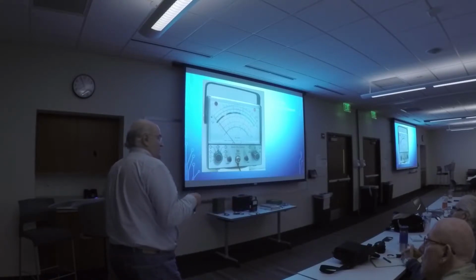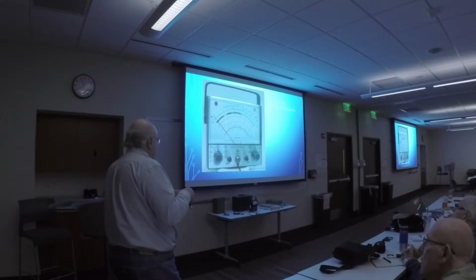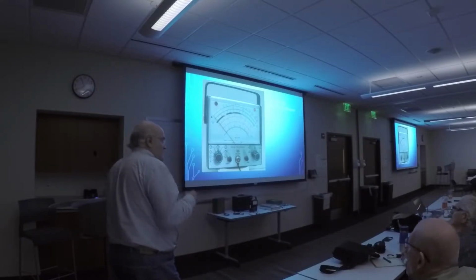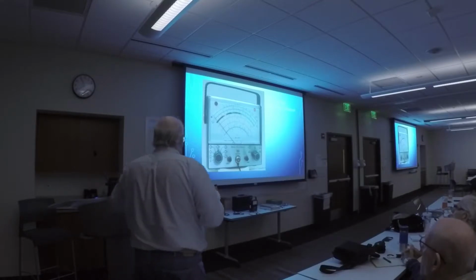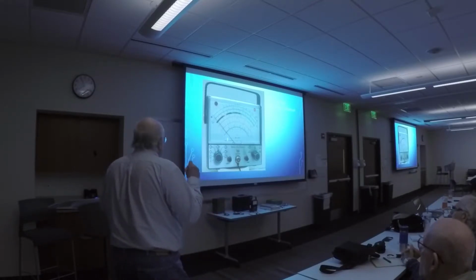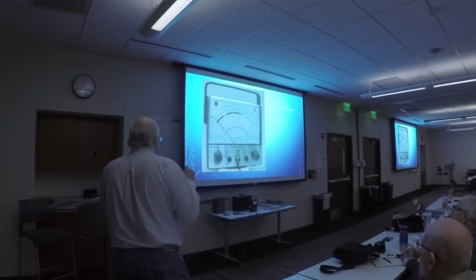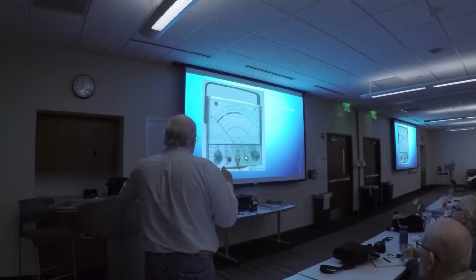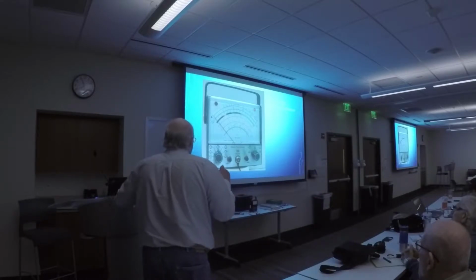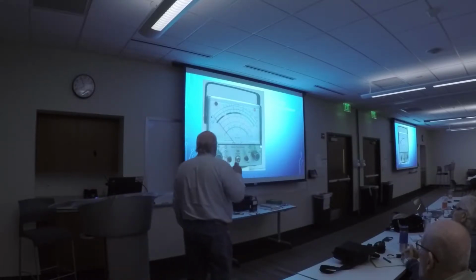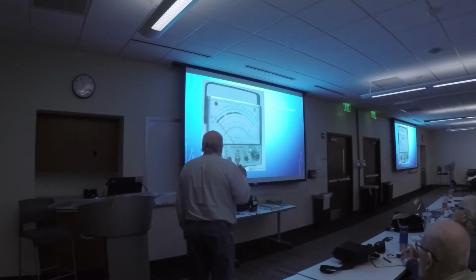You take the isolation lead and hook that to the minus, the negative, the ground, and then you adjust your 0. Because like I said, it's very, very sensitive. It will pick up stuff out of the ether, because it's so very sensitive. Now this center thing here, I'll come back to that in a second. That's an interesting point for this particular one. Now here is your ohm 0, we're talking about that on the Simpson, and then this tells you what you're actually measuring, if you're measuring DC volts or ohms, and it also has an off button.